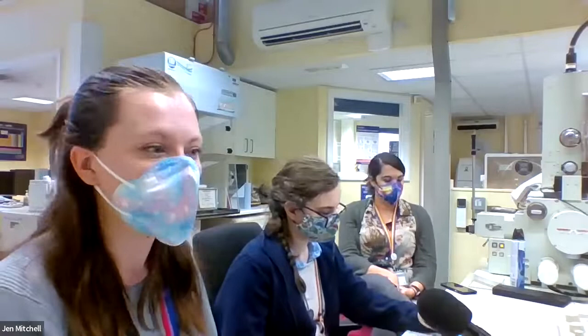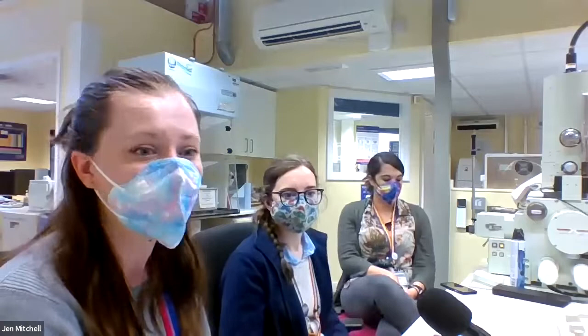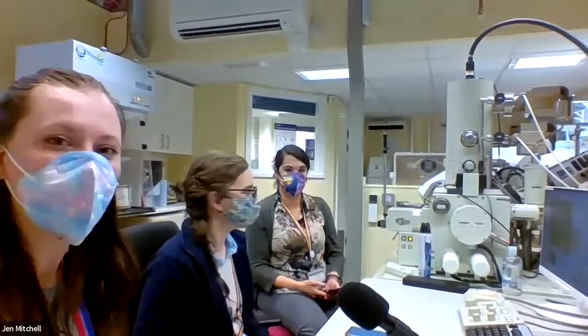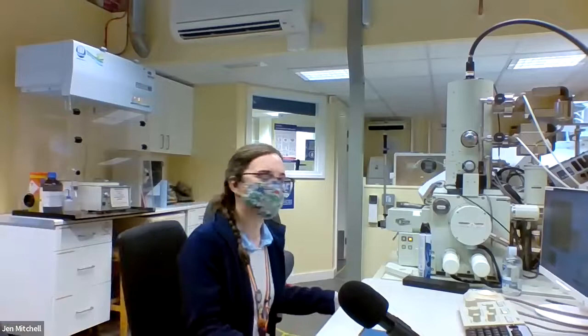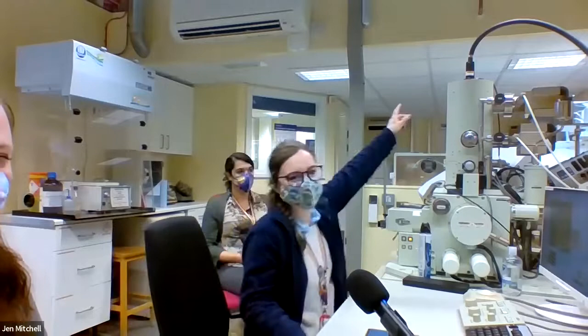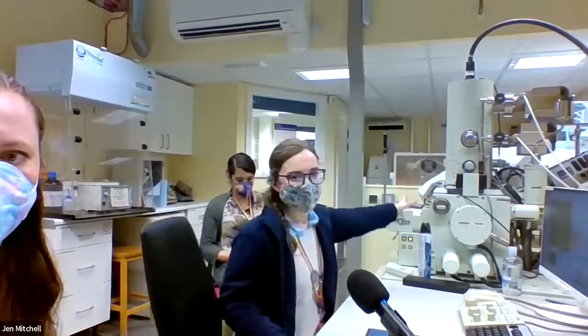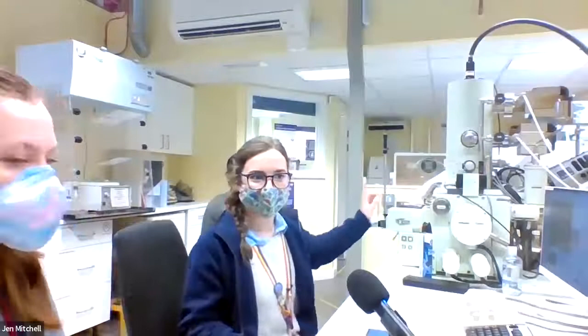Today we're back on our JEOL 7001. JEOL is very kindly sponsoring us and is going to help us bring Microscopy Live to more people, supporting us in our endless endeavours to show you all how electron microscopy works. So today we are using our JEOL 7001, which is our field emission microscope — it can get a much higher resolution and we can look at things in much higher detail than a tungsten microscope. Starting at the top, that's the emission — where our electron beam comes from. Going down the column, there are magnets that align the beam and make it super precise. This here is the sample chamber where our sample is in today, and that's our exchange for getting samples in and out. There are various detectors around that we'll explain as we go along.